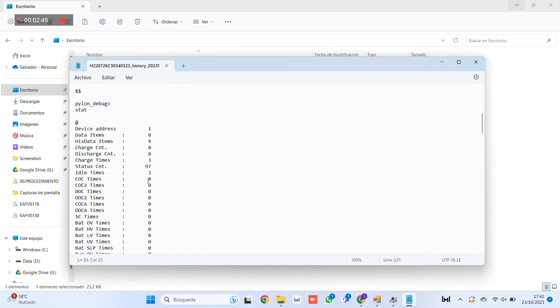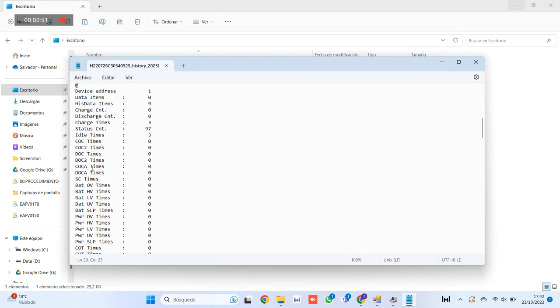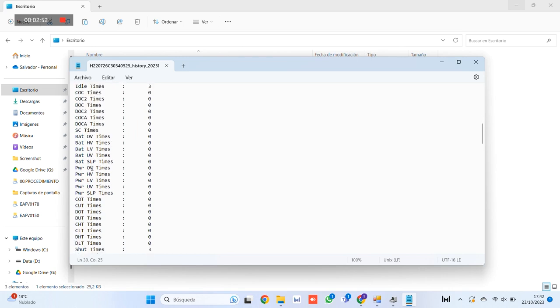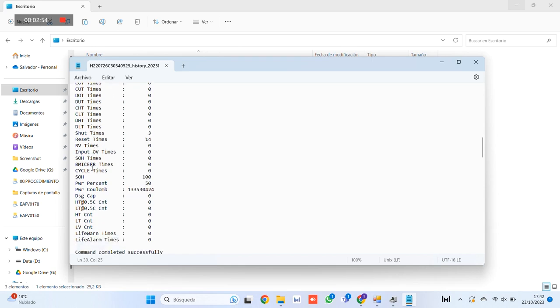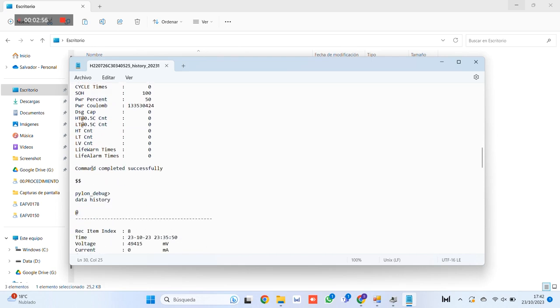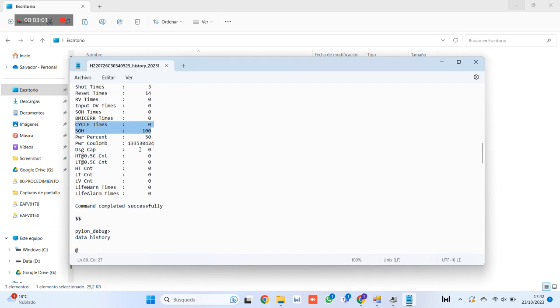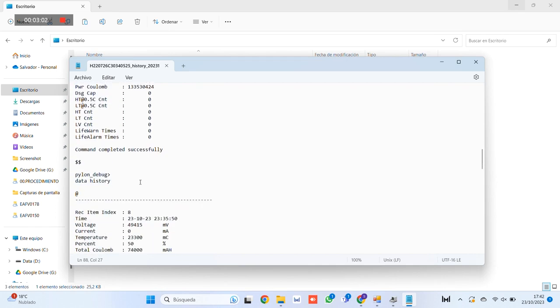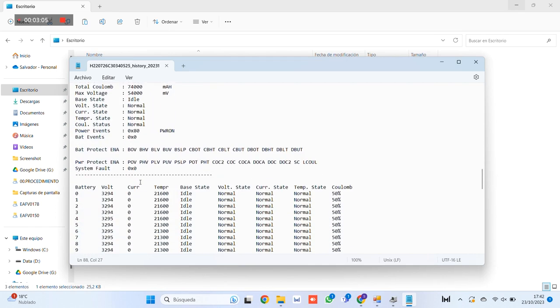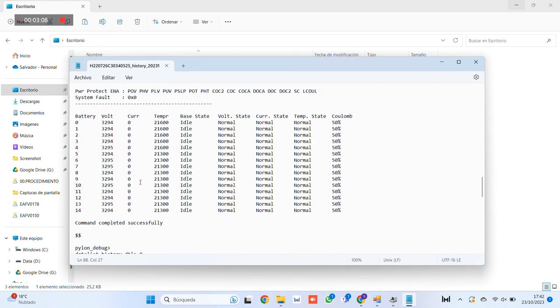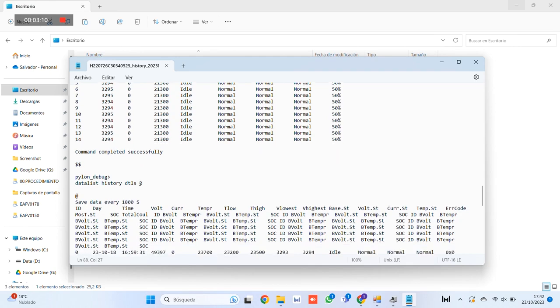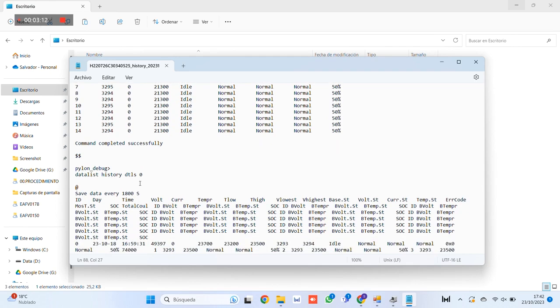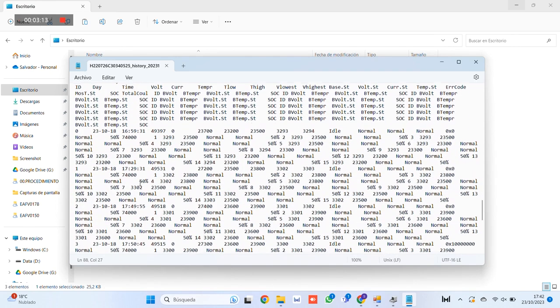This battery, being new, has a number of cycles of 0 and a health percentage of 100%. Finally, if we go down in this same file, current data of all the cells are shown. It shows the normal or fault status if it is the case, as well as more relevant information that will help us to investigate more about the origin of the problems if any in our installed battery.